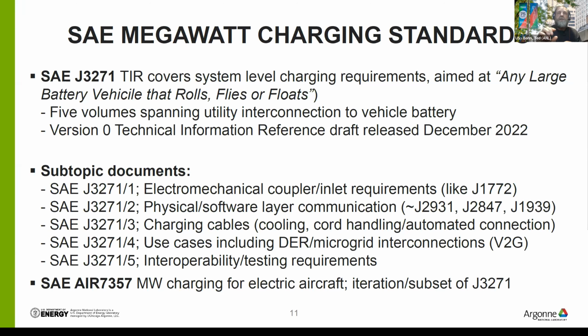The first subsection is purely electromechanical—all the drawings, testing requirements, drive-over requirements, impact drop requirements, anything to do with electromechanical requirements to get to that 3,000 amps. We're going to have 200 amp, 350 amp, 1,000 amp, and 3,000 amp rated connectors with different cooling systems. That document describes how you test them, what the reference devices look like, and all the procedures harmonized with the IEC 63379 and other standards, which are harmonized to that section of this document.